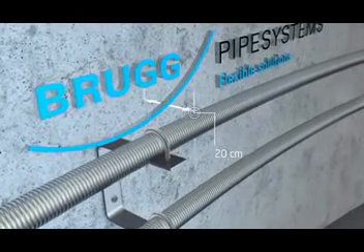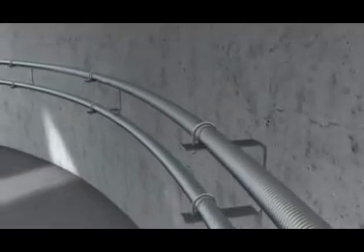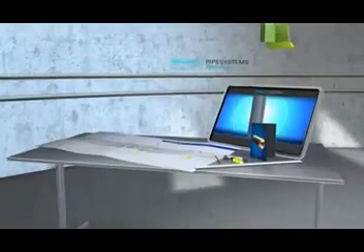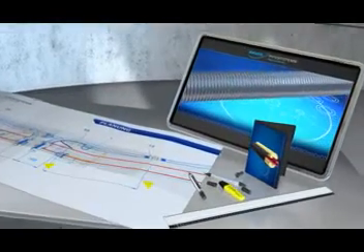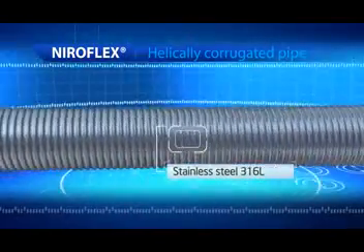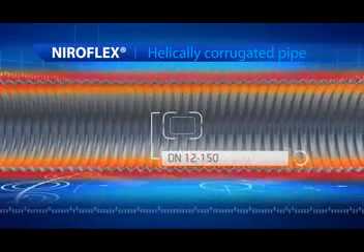Endless production technology makes it possible to install the pipe as one continuous piece — in other words, without any welded joints on the inside. The pipe's flexibility allows for optimum installation and adaptation to the wall contours of the fermenter. High-quality material — stainless steel 316L — and a thin pipe wall thickness of just 0.5 millimeter guarantee outstanding heat transfer.